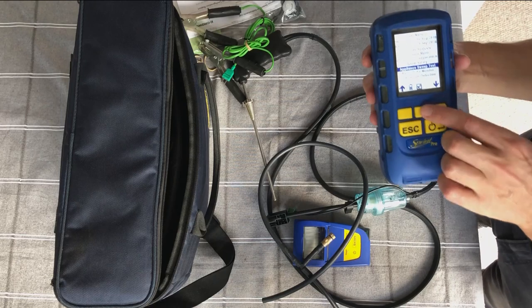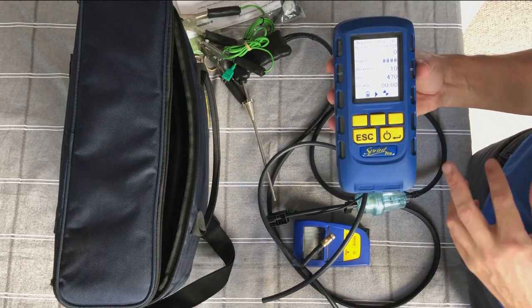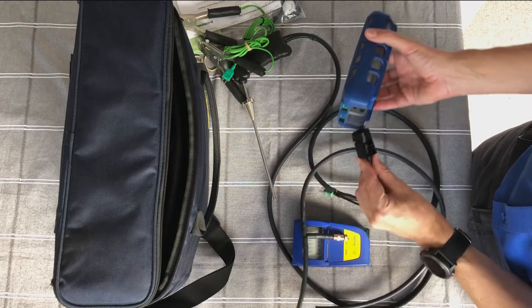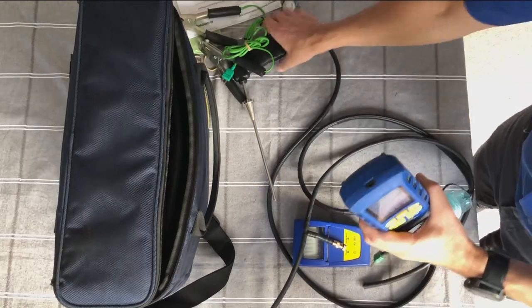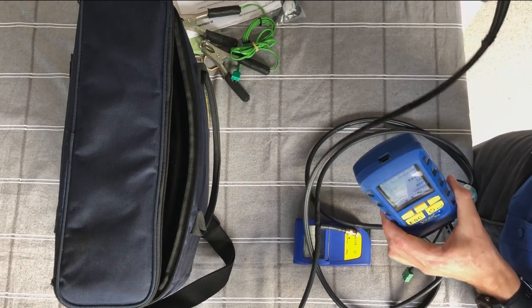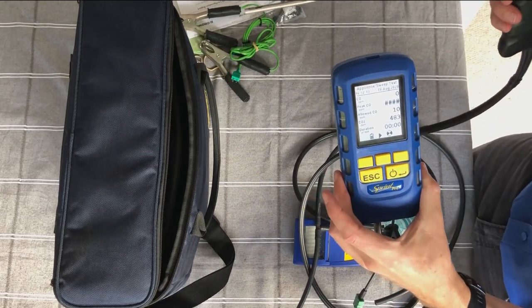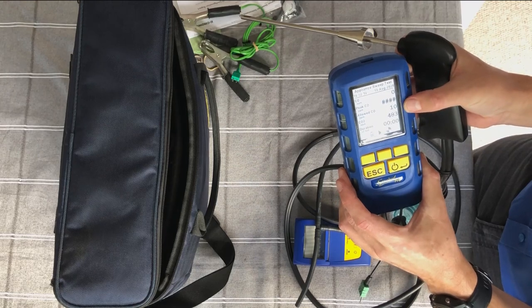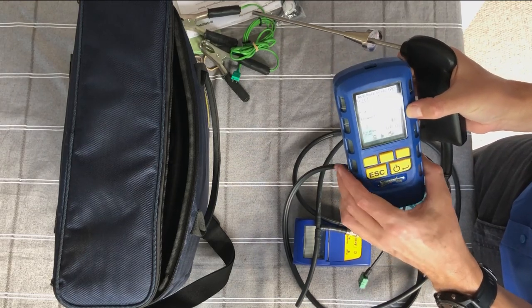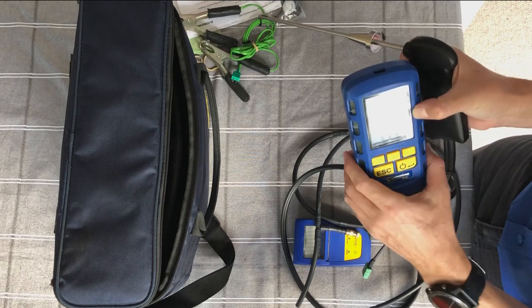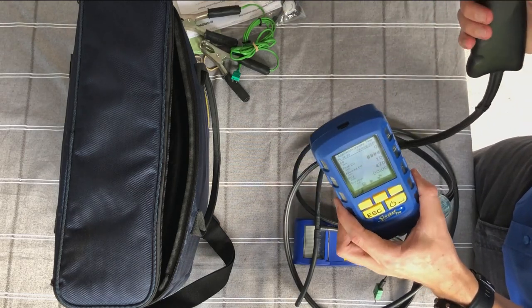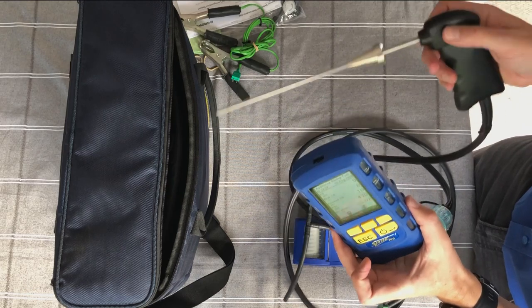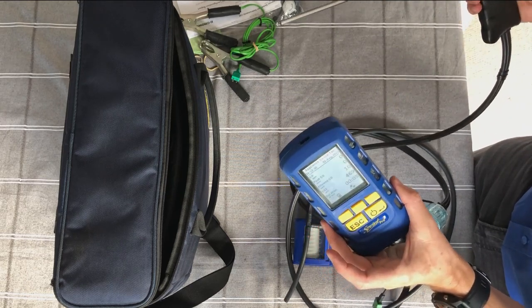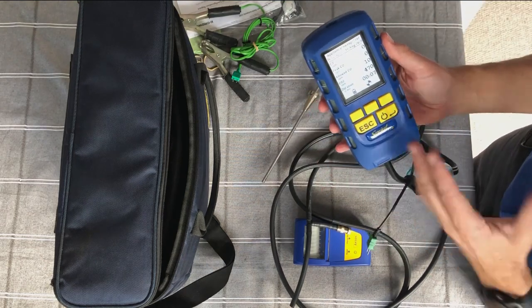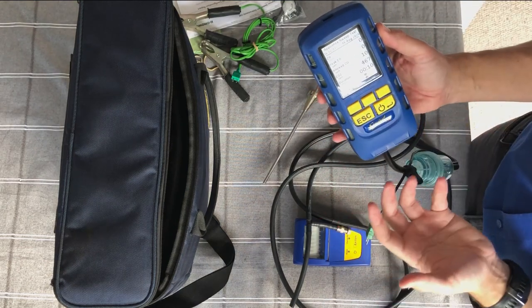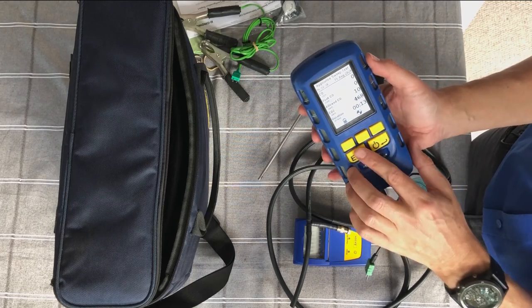Sweep test, this is a new one that again you do as a function of flue gas. So you connect up your flue probe again. But this time what you do is you sweep around the appliance looking for products of combustion. So again, it tells you the maximum you can see is 10 parts per million of CO. I'm currently seeing none. And it allows you to go around and do that test. I think it's a 2-minute test. You hit start when you're ready, and away you go, do your testing and make sure you're not finding products of combustion. So again, refer to your British standard for that, but it's a relatively new sweep test. It's in the software for you to use if you choose to.